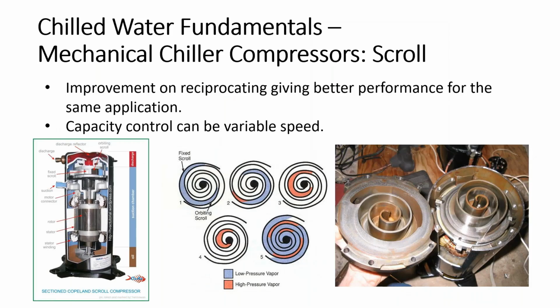So the next upgrade would be the scroll. These are mating, rotating scrolls that actually compress the gas on the high side. One of them mates with the other, kind of what that middle diagram shows, the low pressure vapor and the high pressure vapor. This is an improvement because it reduces the inefficiencies of the reciprocating. They also come in a hermetic version, just like the reciprocating type. You can get them in a semi-hermetic version, but they're fundamentally a closed unit.